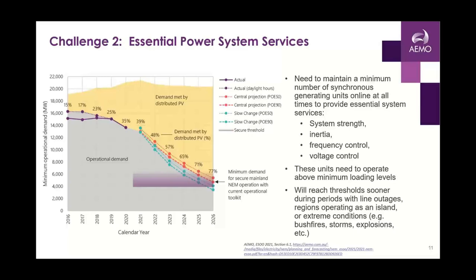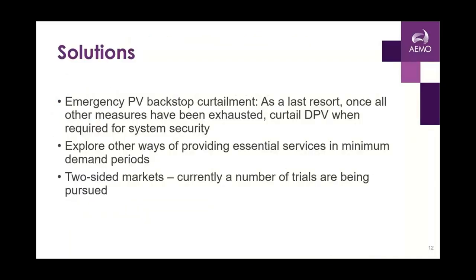Some of these thresholds might be reached earlier if we have some regions in island conditions or bushfires or other situations. So some of the solutions are this idea of having an emergency PV backstop curtailment capability, so actually being able to turn off the PV system. Each system could be controlled by a party to be able to disconnect. We're also exploring other ways of providing minimum essential system services in those minimum demand periods. Can we get them from other types of generators, or what other network devices do we need? And can we look at options like two-sided markets to help prevent these situations even arising, so that distributed PV becomes part of the wholesale market and isn't incentivized to be operating at those times.